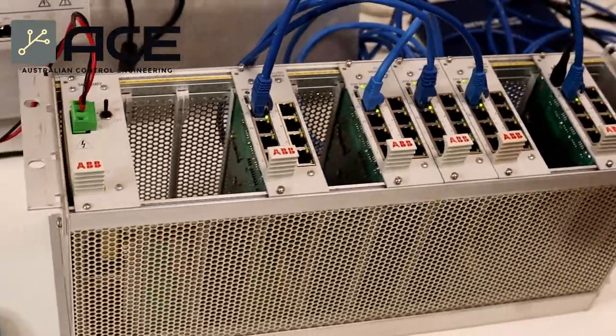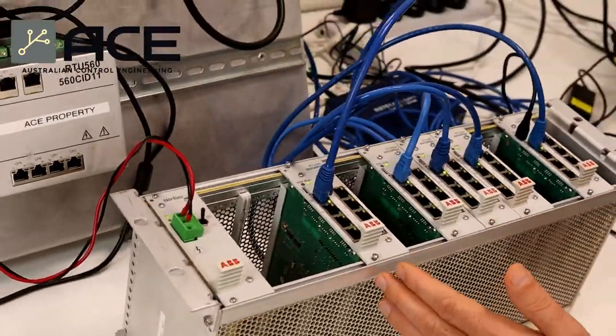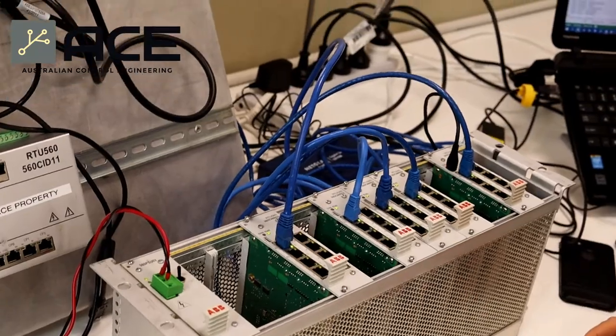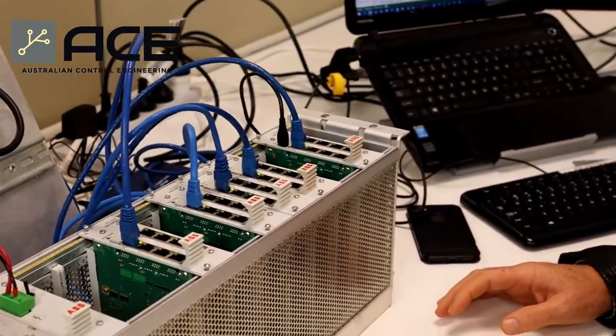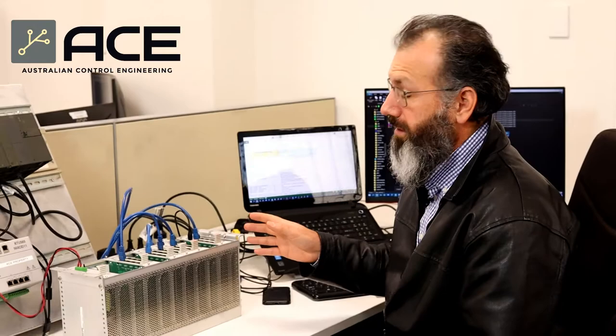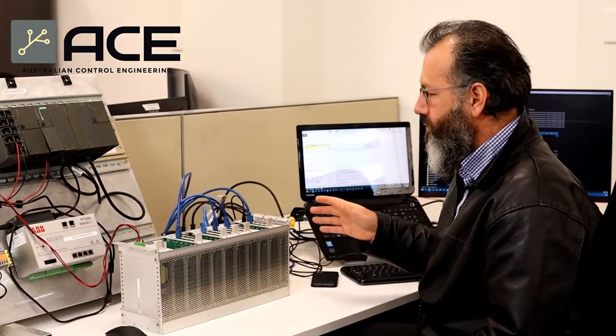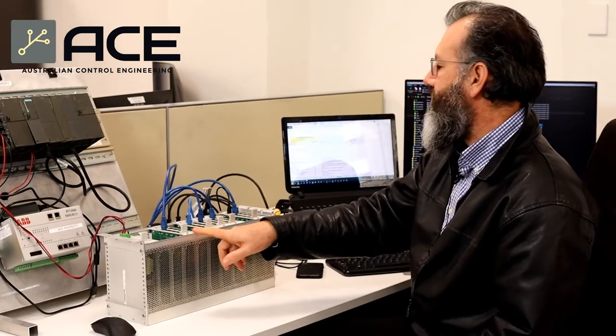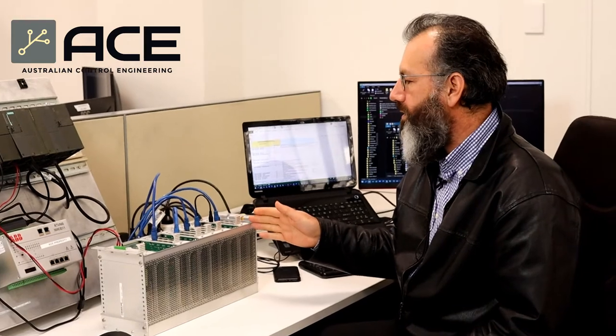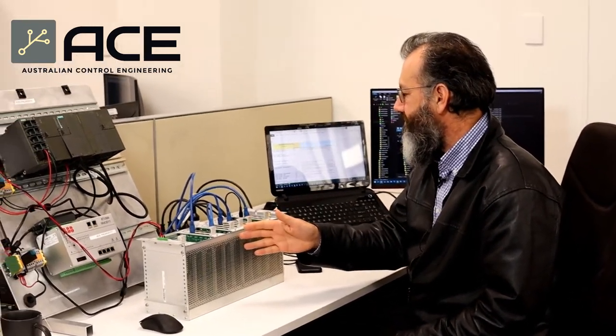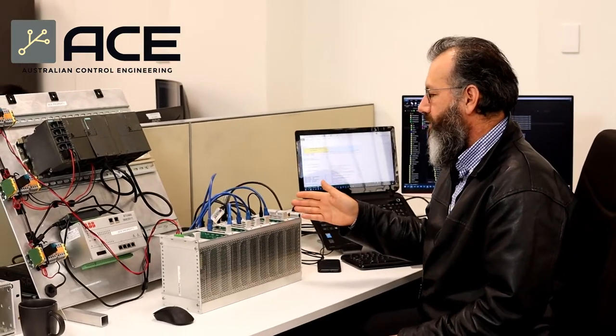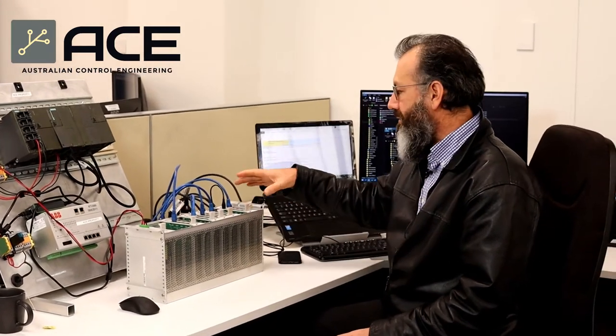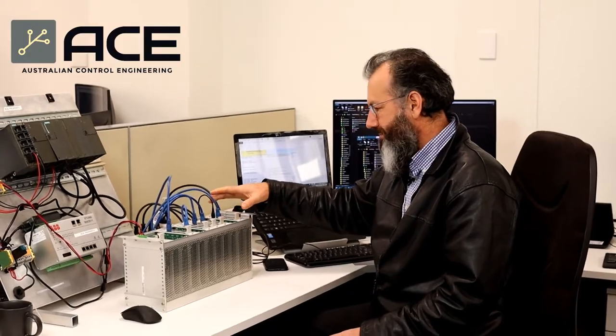The other issue we encountered is that the CPUs we had were set up with different passwords, so we had to harmonize the passwords — that's the technical term. The other issue was that one of the CPUs had a slightly older firmware, and that would stop all the CPUs from synchronizing. Once we upgraded the firmware of that card, all the other cards synchronized automatically with the primary card.